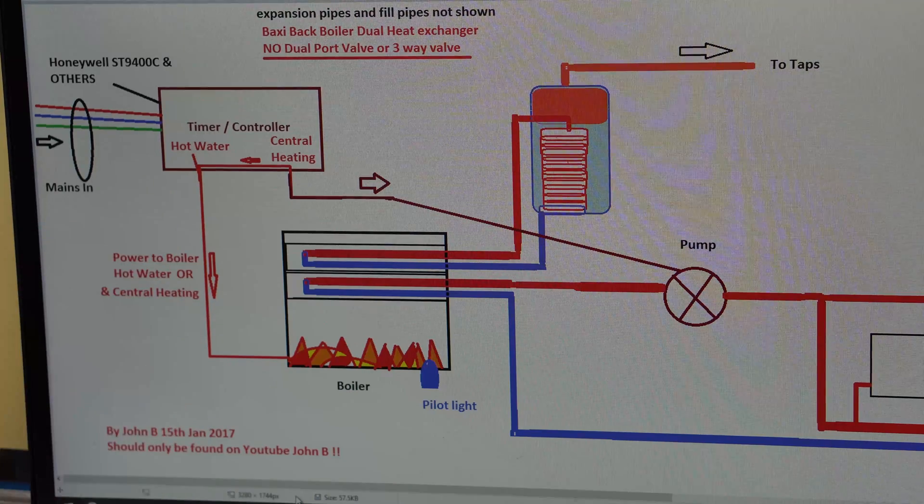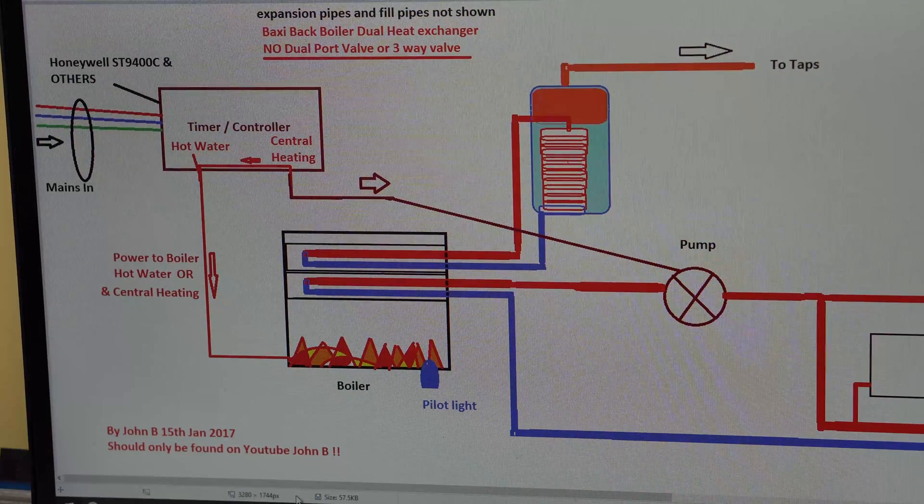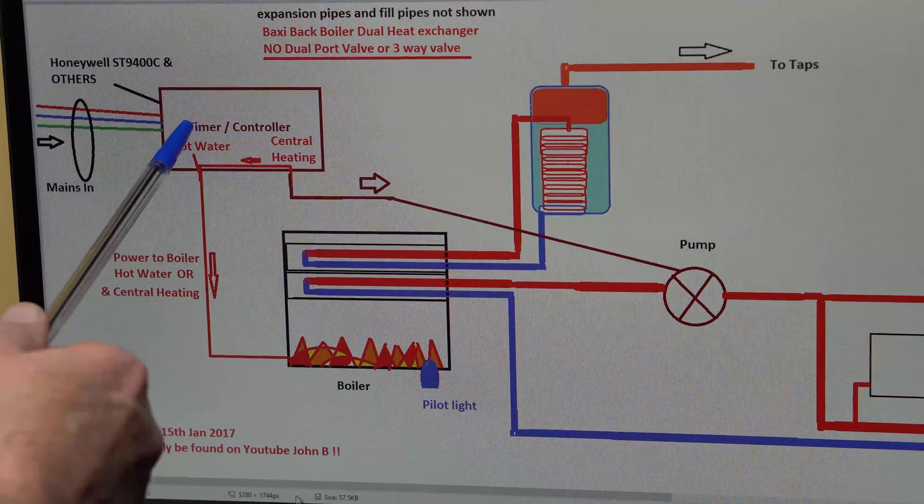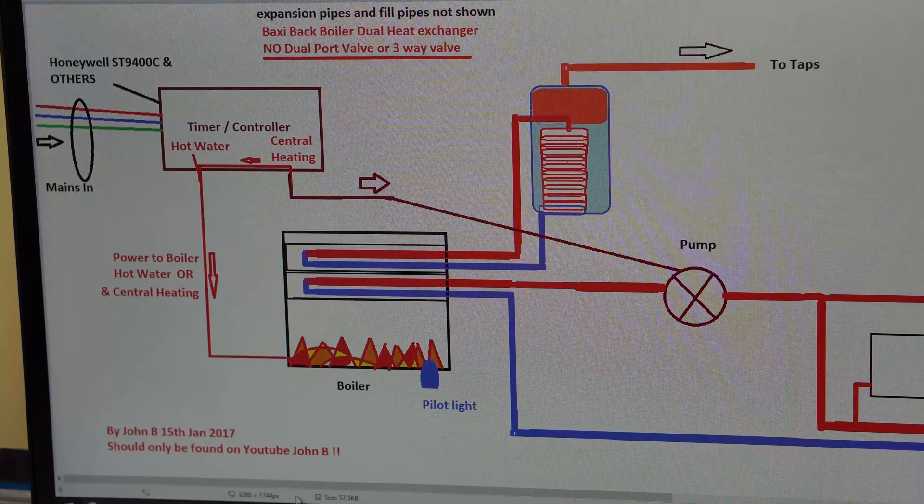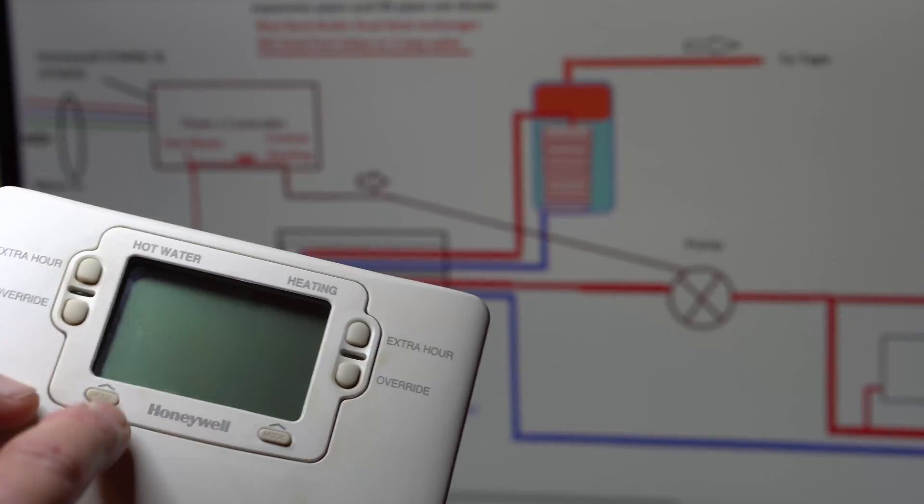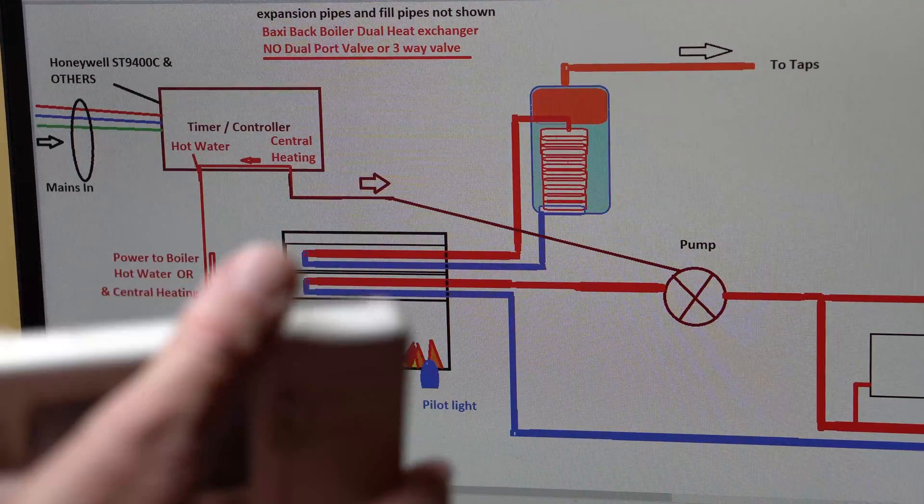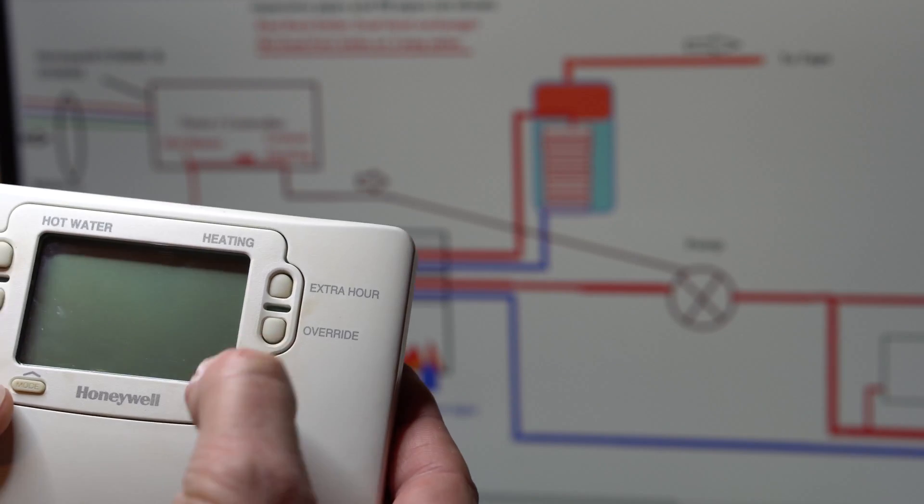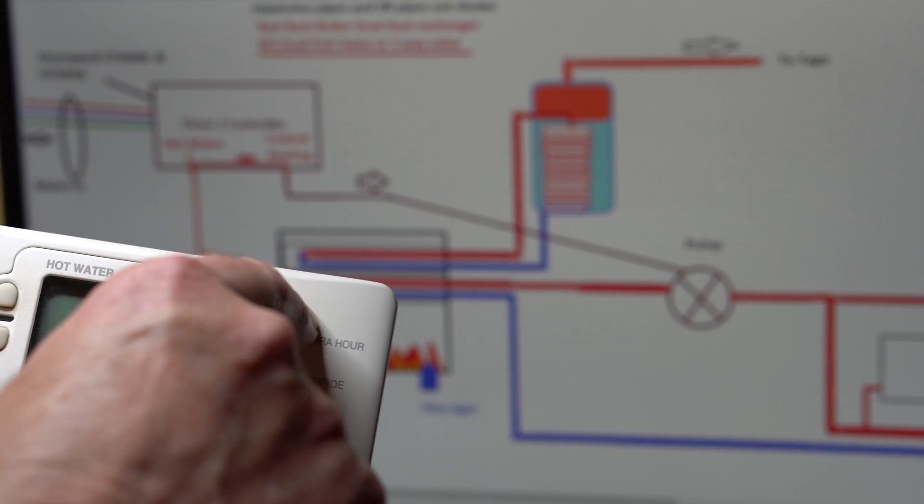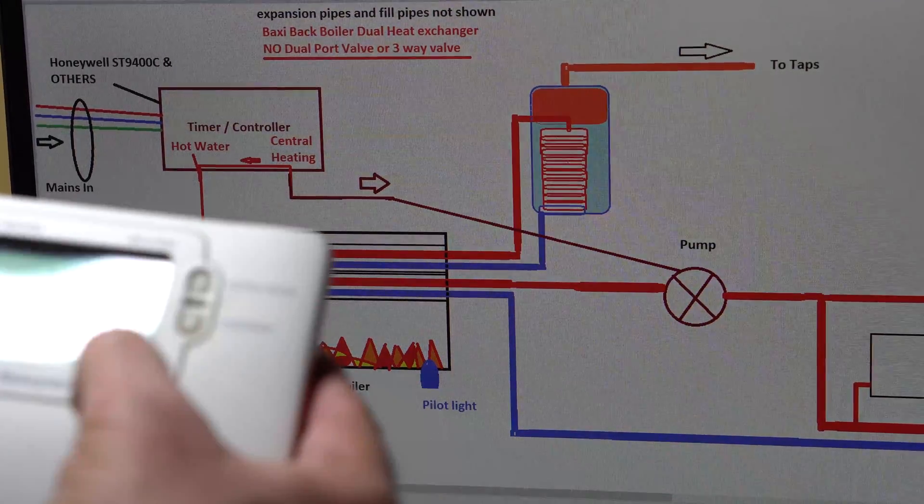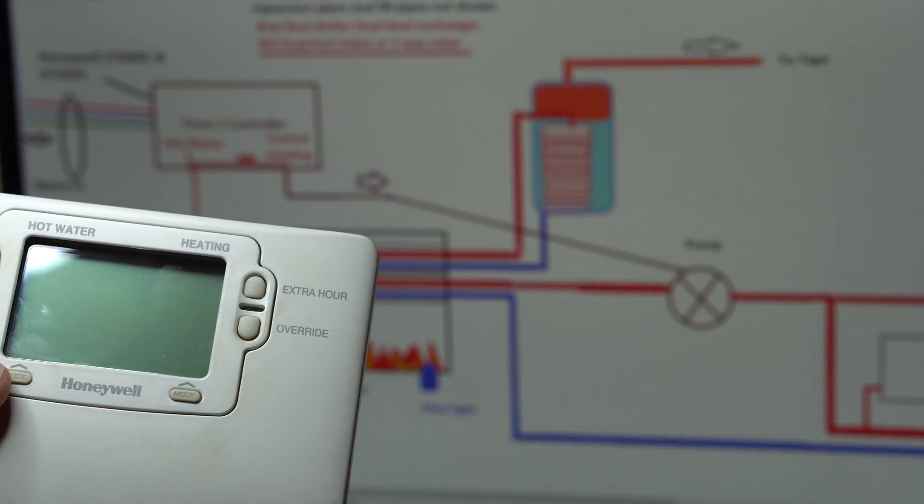So if you've got Honeywell timer and it's over four or five years old, that's the first thing to check. Check the supplies coming out. Incidentally, this timer, you could actually hear, when you press hot water, you could hear the relay click. And then when you press the override for the central heating, in the early days, you could hear the second relay come in to bring on the pump. And then last night, zero degrees out, 20 to 12, press it, no relay for the central heating.